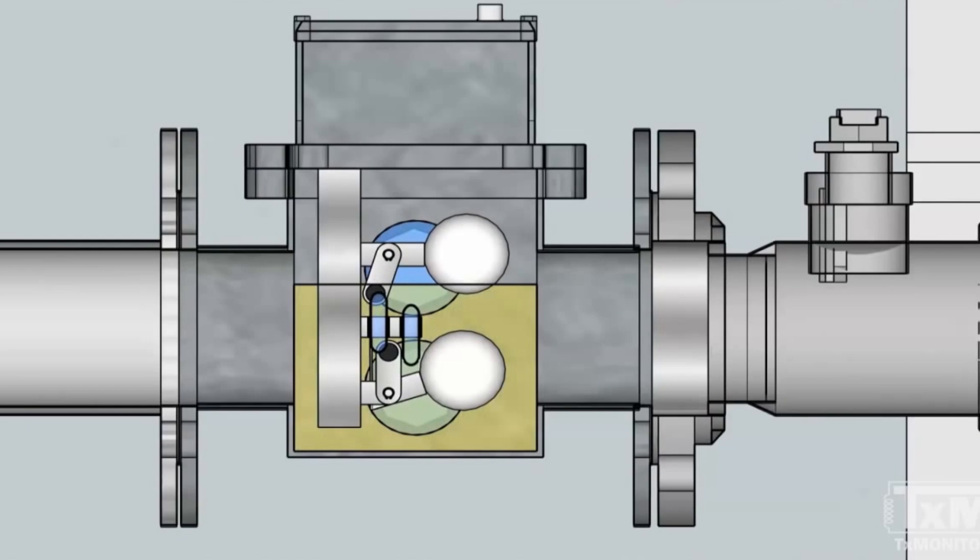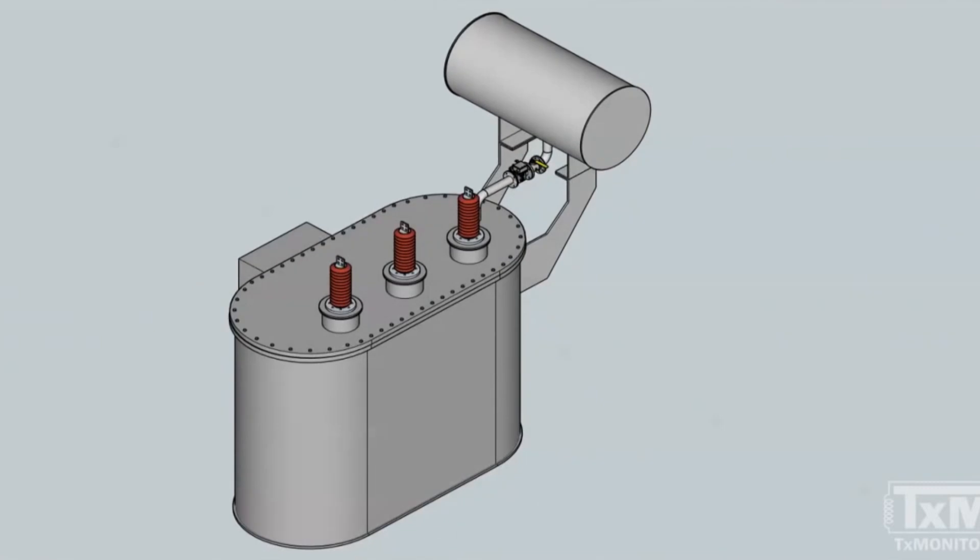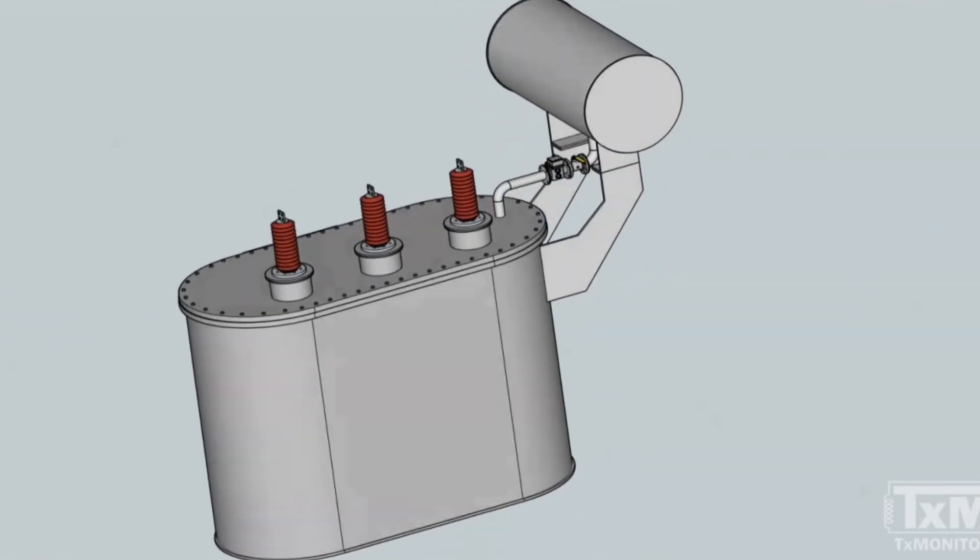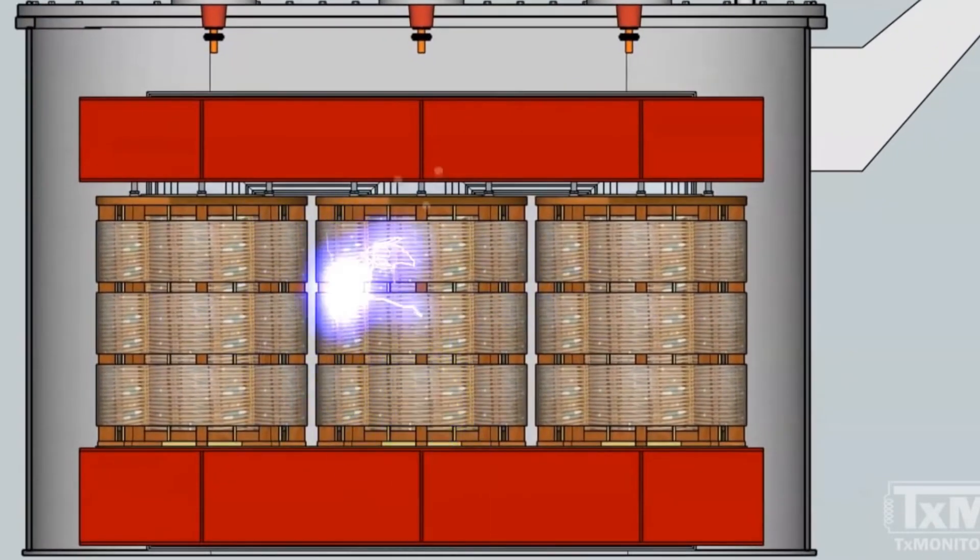It is on this pipe where the Buchholz relay is typically installed to trap the bubbles before they reach the conservator tank. These free gases are commonly the result of abnormal conditions inside the transformer and are also useful in the diagnosis of these conditions.